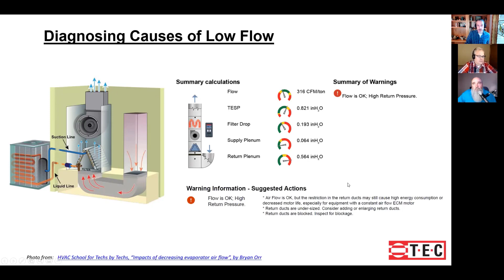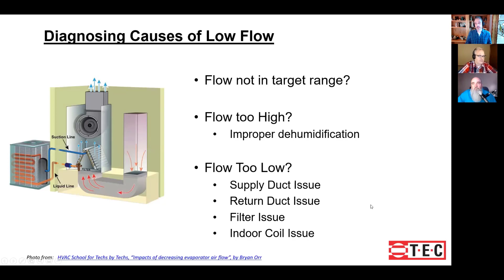So again, we're coming back to, we want to know if flow is in the right range. If it's too high or too low, what's causing it? This app will help you understand, do I have a supply duct issue, a return issue, a filter issue, a coil issue? Am I flowing too high maybe? And that's why I'm not getting the right level of dehumidification or latent work being done. So it's really got a lot that will help us with that. Steve, maybe you can take us through kind of a screen by screen tour of the app.